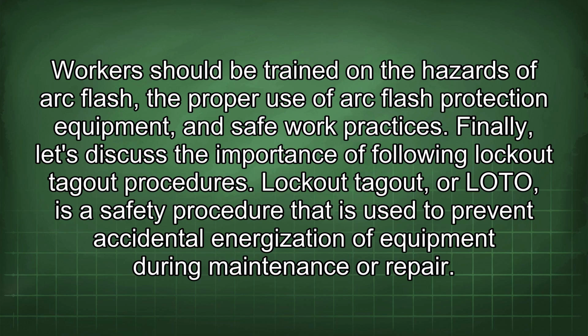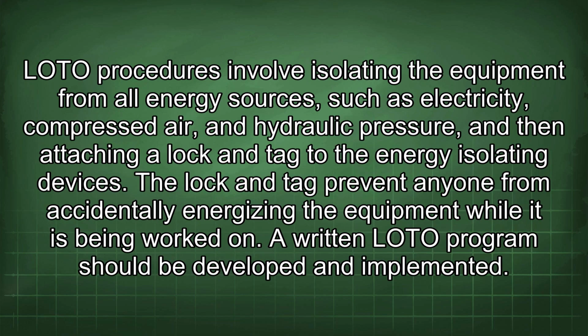Lockout-tagout, or LOTO, is a safety procedure that is used to prevent accidental energization of equipment during maintenance or repair. LOTO procedures involve isolating the equipment from all energy sources, such as electricity, compressed air, and hydraulic pressure, and then attaching a lock and tag to the energy isolating devices. The lock and tag prevent anyone from accidentally energizing the equipment while it is being worked on.